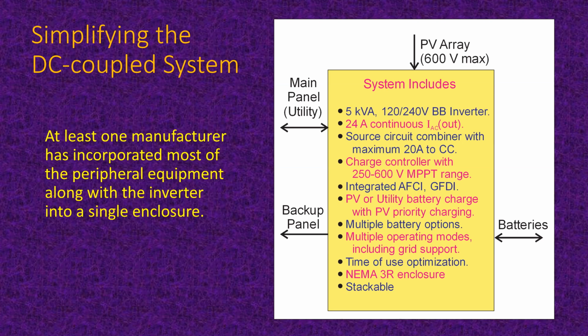And by the way, the batteries now don't connect with 175 amps at 48 volts. They connect up with maybe 30 amps at 400 volts instead. And since it's an integrated package, it's okay to do that. You don't have these fancy rules about extra switches for every 48 volts of batteries. Backup panel connects directly, and the main panel connects directly. So this is a pretty slick operation. Let's take a look at one.